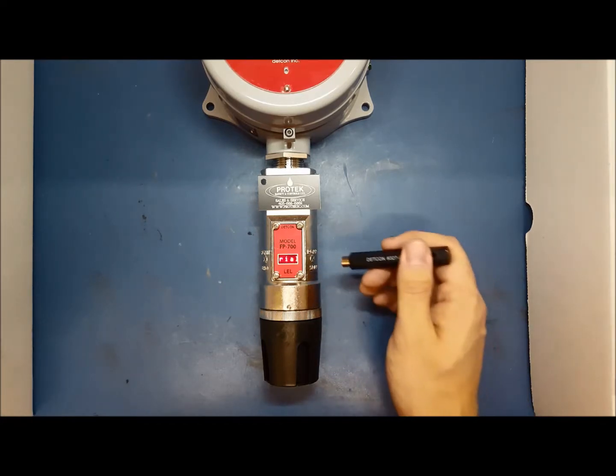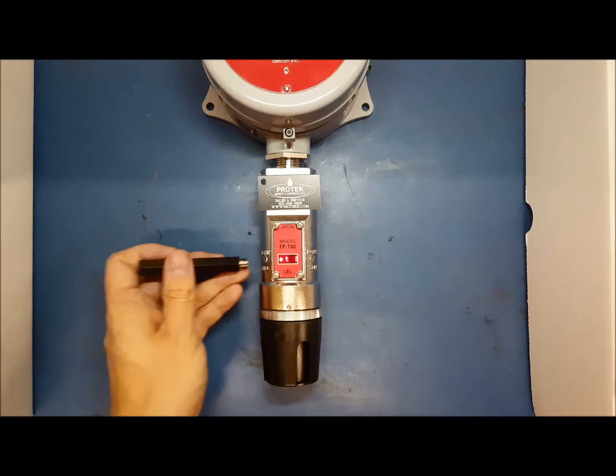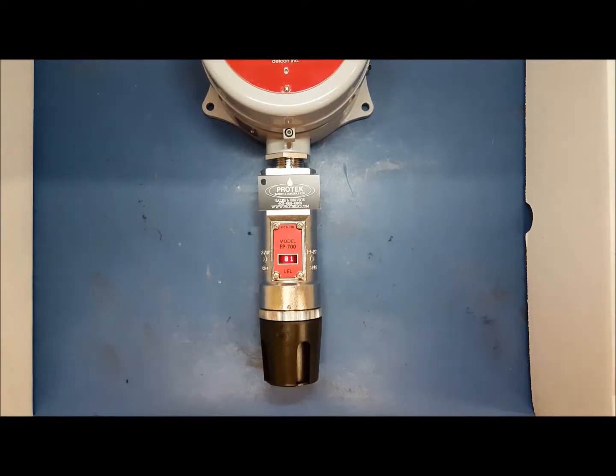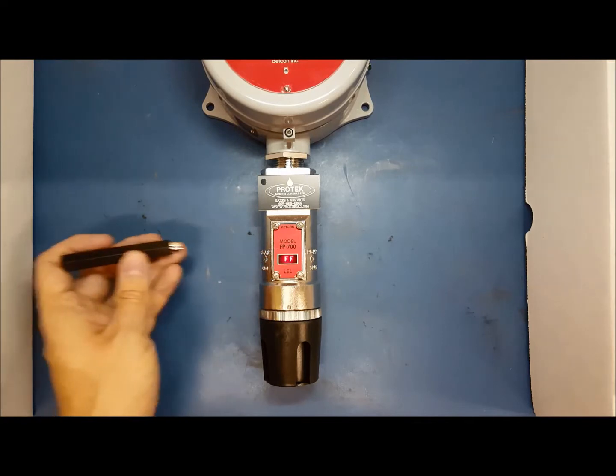Now hold the magnet over PGM1 for about 5 seconds. An arrow will point left on the display, indicating you are interacting with PGM1. Wait until the display reads Set ID. The display will now read the current ID setting.